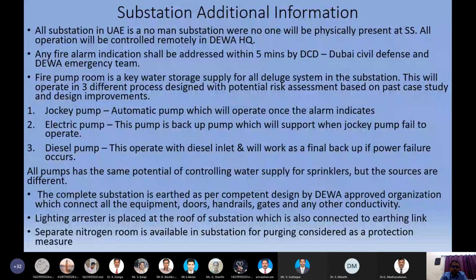Any fire alarm indication shall be addressed within 5 minutes by DCD, which is Dubai Civil Defense, and the DEWA emergency team. So any kind of fire in the substation, in any zones or any loops, they will reach the area within 5 minutes. That is the maximum time given by the DCD. And the fire pump room is a key water storage supply for all the fire systems in the substations, which is operated in 3 different processes, as I said: jockey pump, electrical pump, and diesel pump. All pumps have the same potential of controlling the water supply for the sprinklers, but the power sources are different.